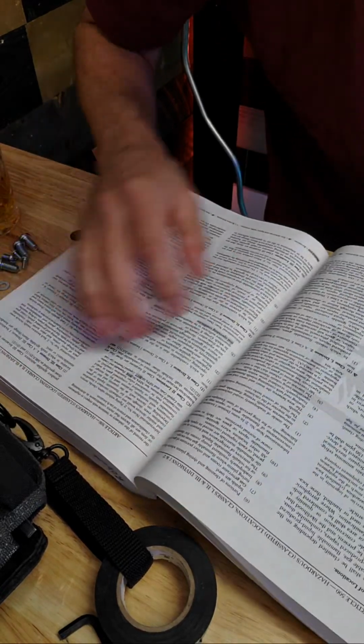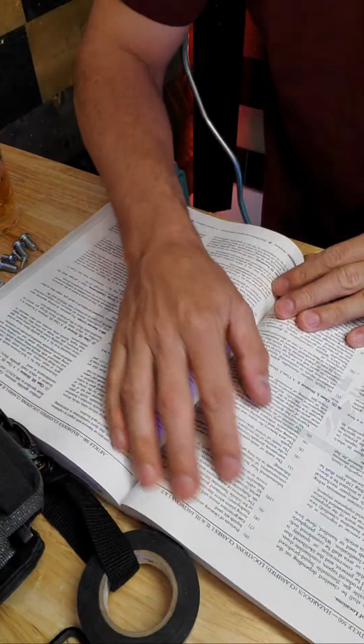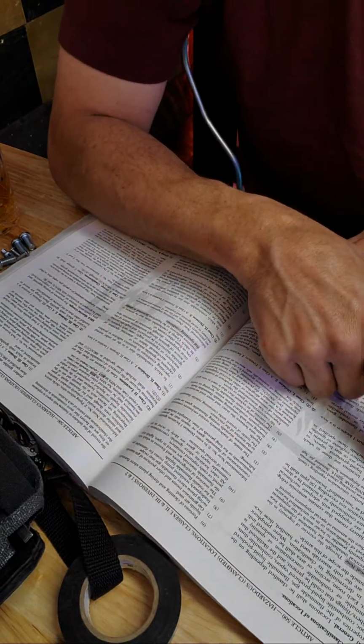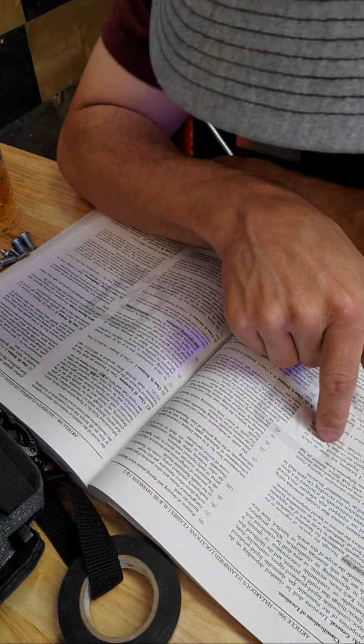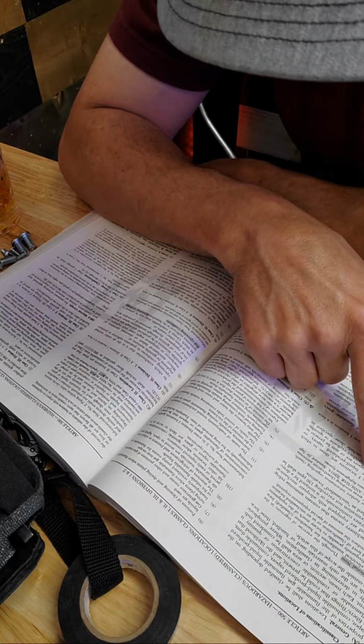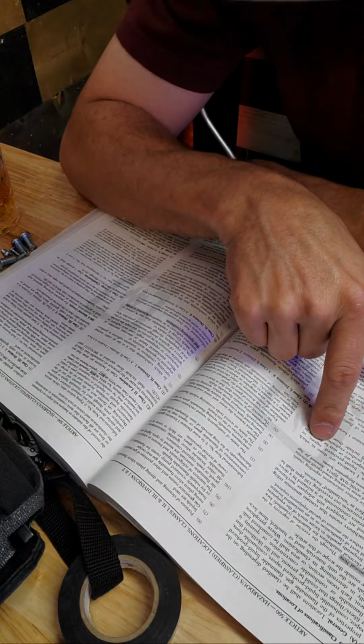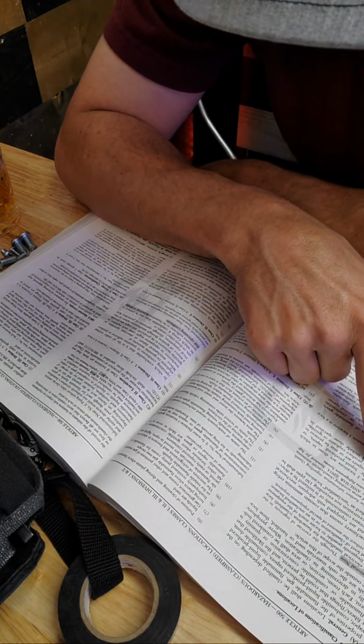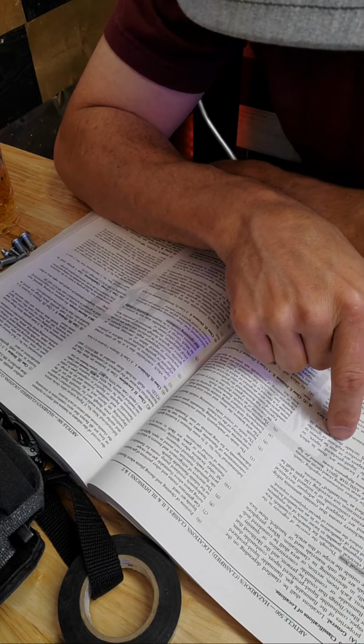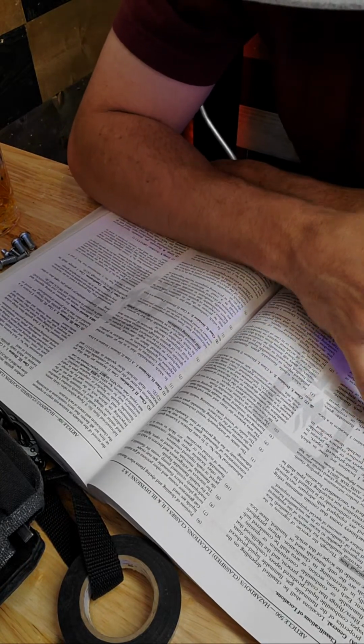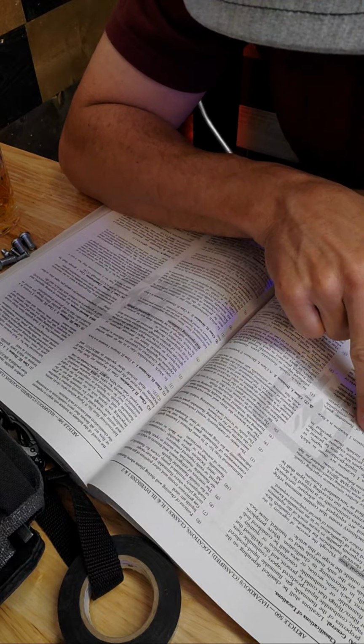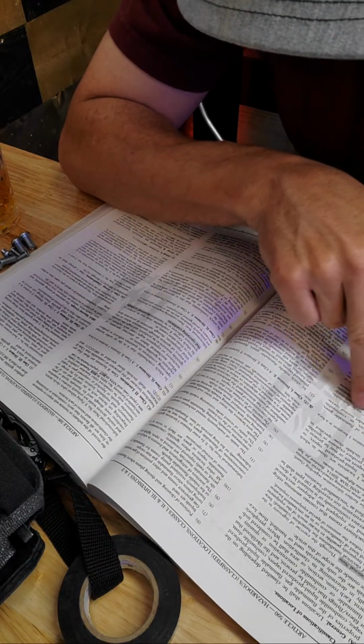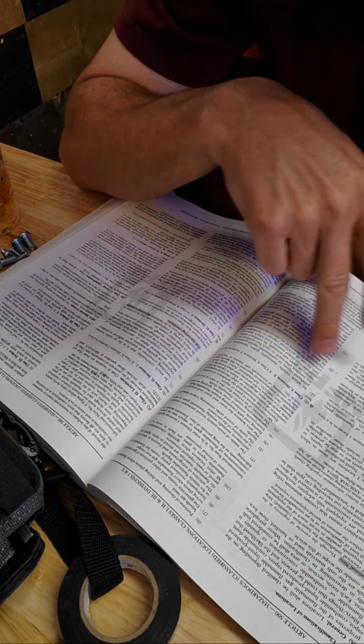So what we're looking for right now is we're trying to figure out what location. So first off, we've got Class 1 locations. Class 1 locations are flammable gases, flammable liquid produced vapors, or combustible liquid produced vapors may be present. And then a Class 1 Division 1 is ignitable concentrations, flammable gases, things like that. So we know we're not that one.